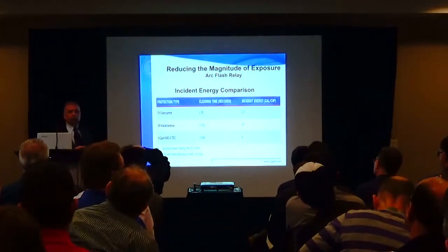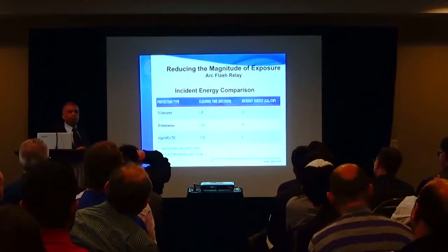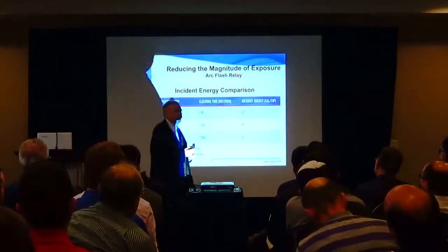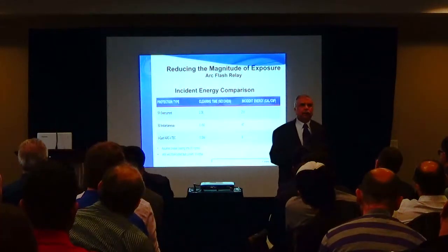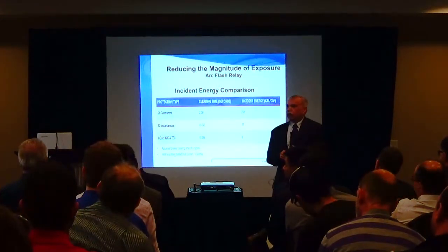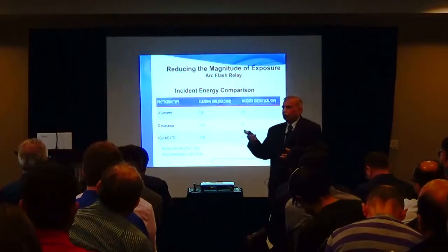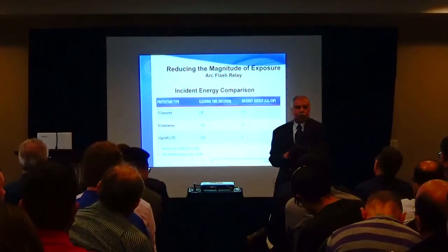But this is using a spot between the secondary of the transformer and the breaker. You just use that spot, right? This is detecting on the line side of the breaker to trip the high voltage side of the transformer. Okay, so you need an interrupter. That's on the high side. It's on the high side. So the tripping occurs on the high side, the fault could be on the low side, on the line side of the main breaker. Yeah, correct.